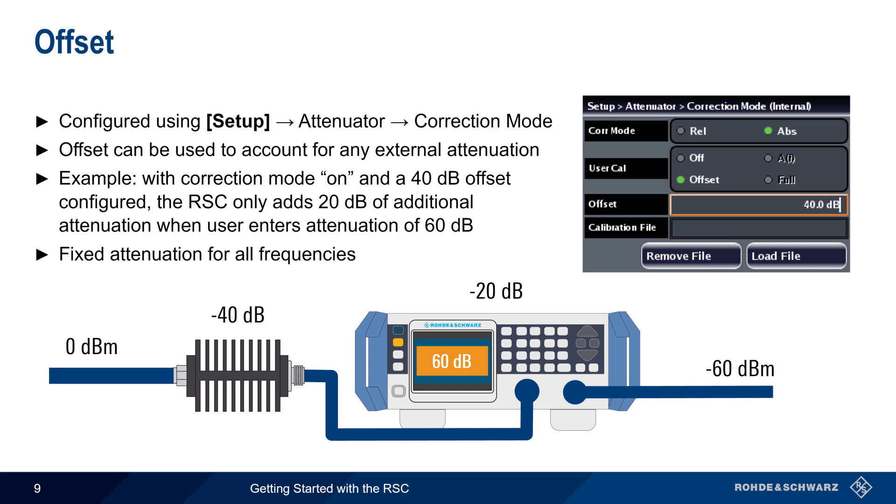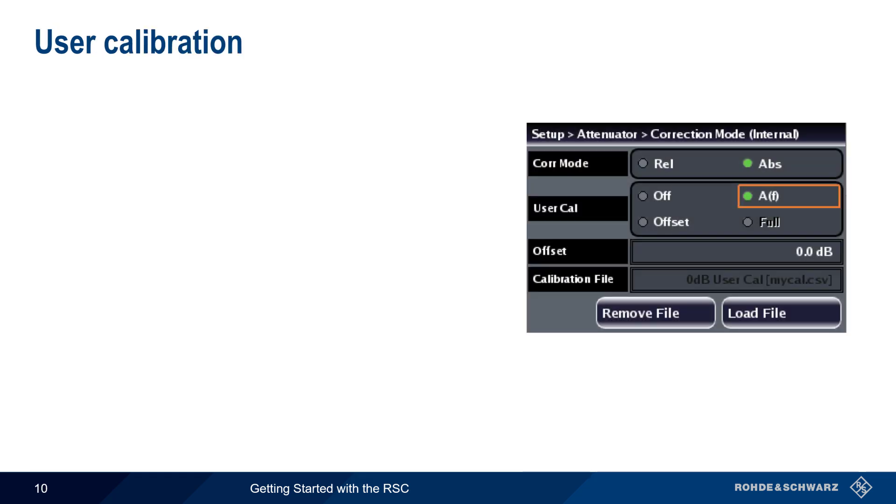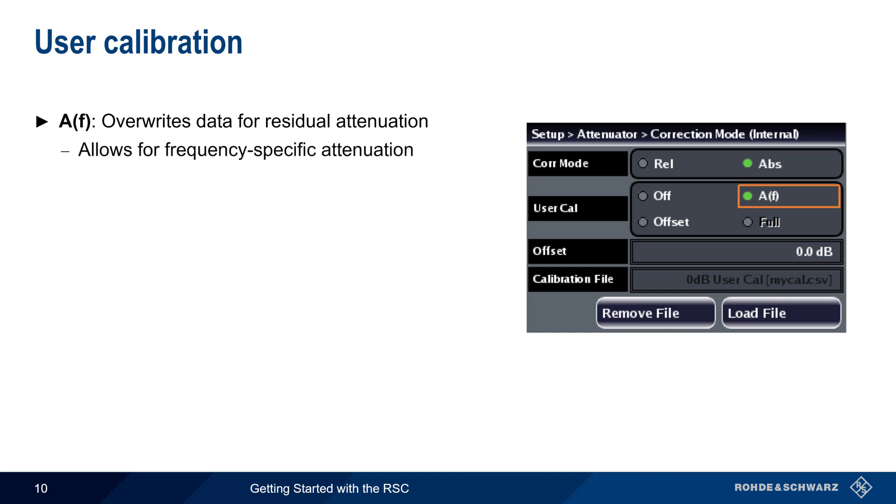In order to have a frequency-specific external offset, a user calibration could be used. There are two types of user calibration. The first, A(f), overwrites the data for residual attenuation — this is the attenuation from the RSC's internal cabling, connectors, etc. at different frequencies. Therefore, this type of calibration can also be used to provide offset values for frequency-specific external attenuation.